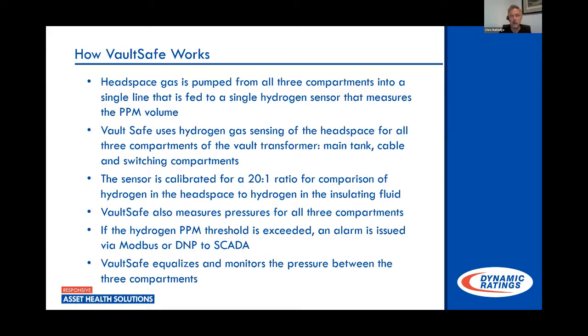So now we've kind of turned it into your substation situation where you have nitrogen-fed systems. Again, these aren't nitrogen supplied, but they should have nitrogen placed on them and oxygen purged off when they're in service. But some adapters were made to fit into the gas sampling ports of these, and also one can go in the fill valve of the cable compartment. So I was able to effectively manifold everything together in the headspace, which now let me also pressurize that cable compartment, which was something we had not been able to do in the past.